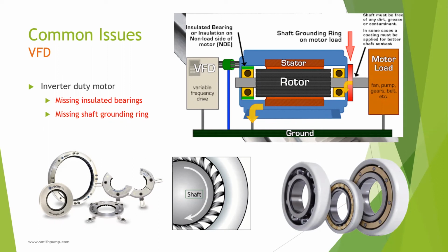This ring has tiny carbon brushes that make physical contact with the shaft and is usually installed on the motor drive end. The grounding ring is secured to the motor frame and electrically connected as well. So this shows the final electrical path for safe rotor grounding through the motor frame. It's a simple yet cost-effective way to prevent premature motor failure.